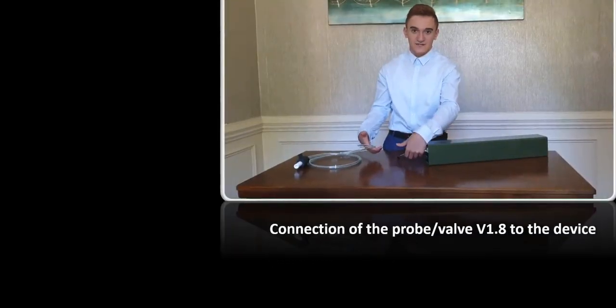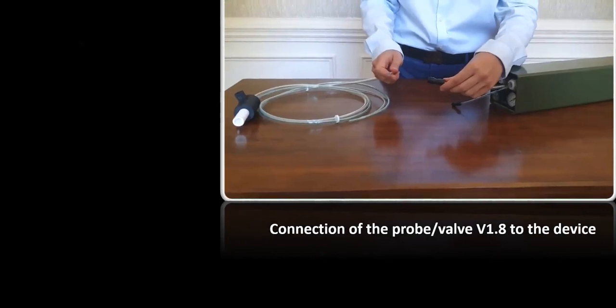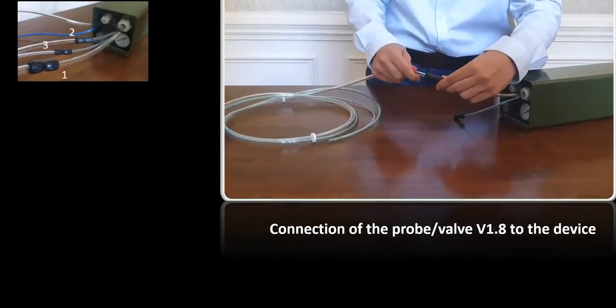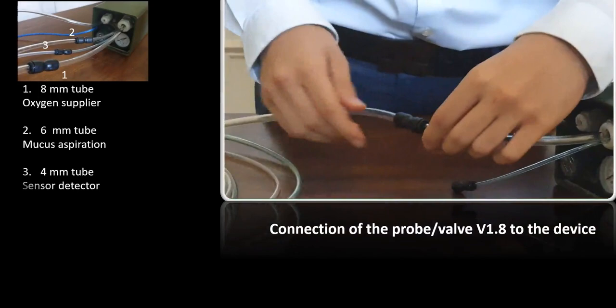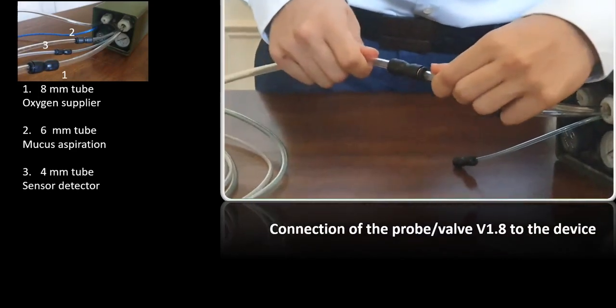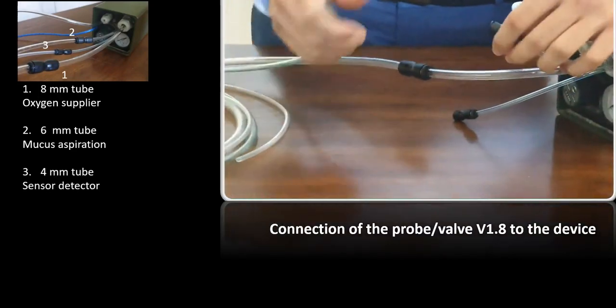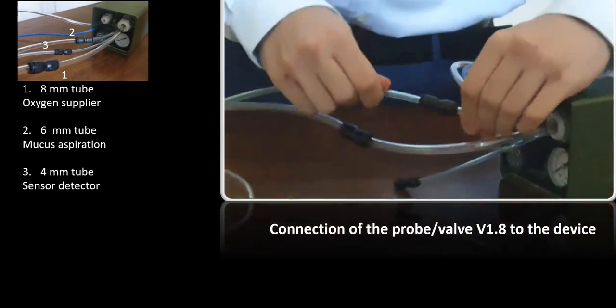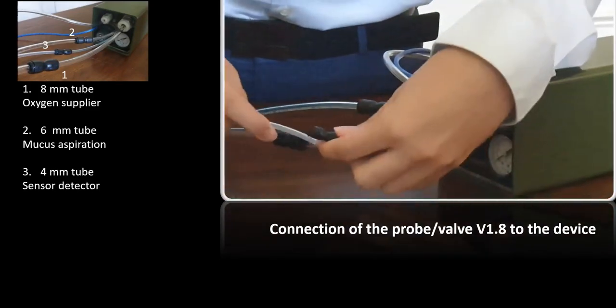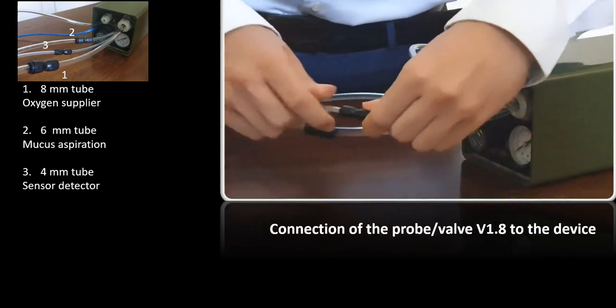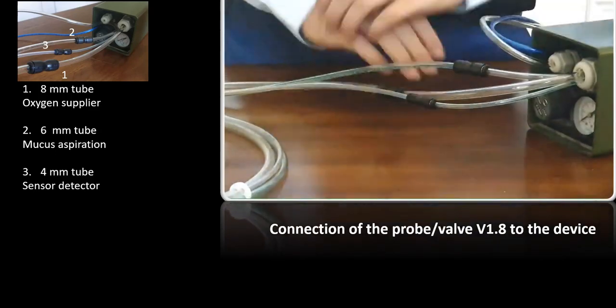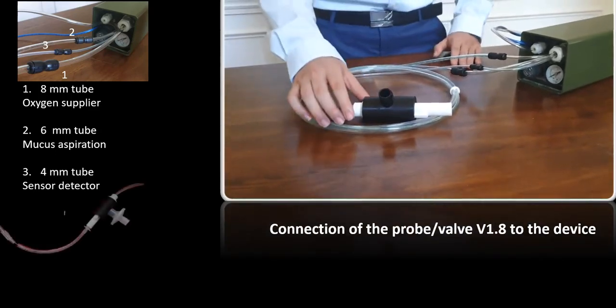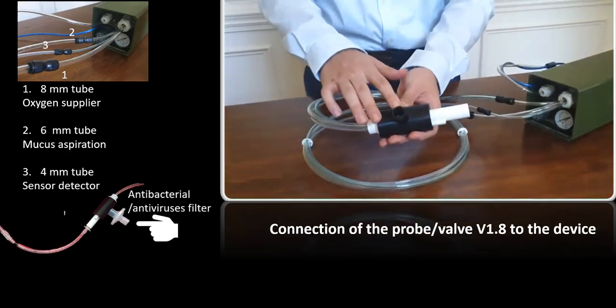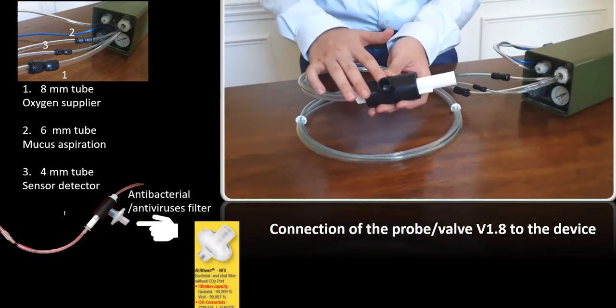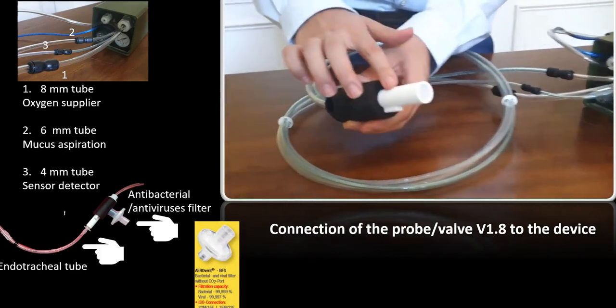Now, connect the tubes of the probes to the respective connections on the device. Connect each one singularly, exerting a soft traction each time to make sure it's connected properly. Now, here connect the antivirus and antibacterial filter, and here the tracheal tube.